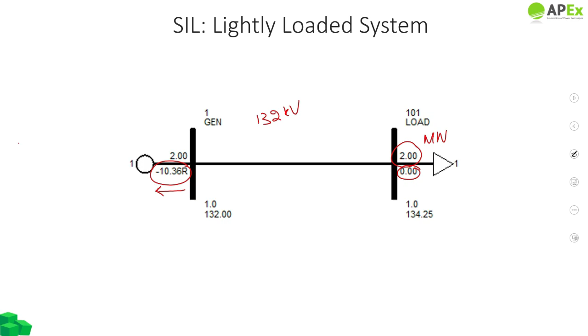However, we can see that this line is supplying minus 10.36 megavars. The minus sign shows that this generator is basically absorbing 10.36 megavars. And since the load is not producing it, then it must be the transmission line that is producing these megavars. So what happens at the receiving end? We can see that our voltage is now up to 134.25 kilovolts. So this is greater than the sending end voltage.